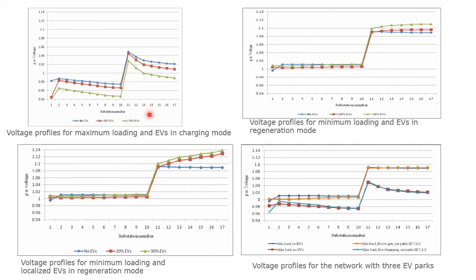So what happens when the grid has maximum loading and the electric vehicle is in charging mode? At that time, in the UK the lower limit is 5% of the nominal voltage, and in this case some substations are getting close to 0.94 per unit. So this is in violation. With 30% electric vehicles and maximum load, some substations go below that 95% even with a load tap changer.